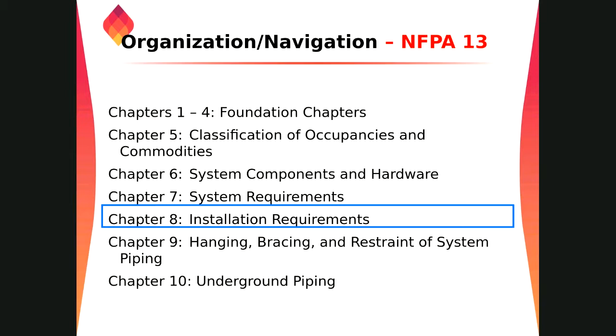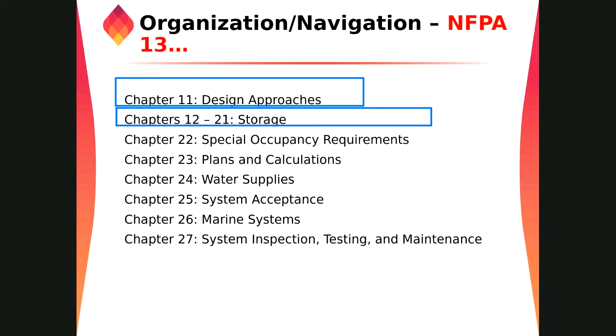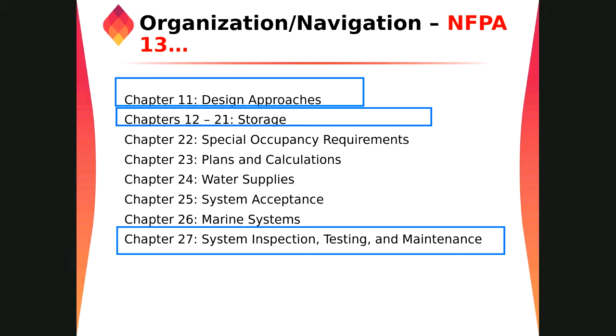Chapters 12 to 21 are totally based on storage occupancies, right? So from here all the way up to the 21st chapter is based on the different storage, different requirements and criteria. Chapter 23 talks about the plan and calculation, right? So your plan and calculation of the system should be based on chapter 23, and 24 is for the water supply, 25 for the acceptance testing. Suppose you install your system; before you put the system into service, we have to go for the acceptance test. Chapter 26 is for the marine system, and 27 is for ITM, inspection, testing and maintenance of water-based sprinkler systems.